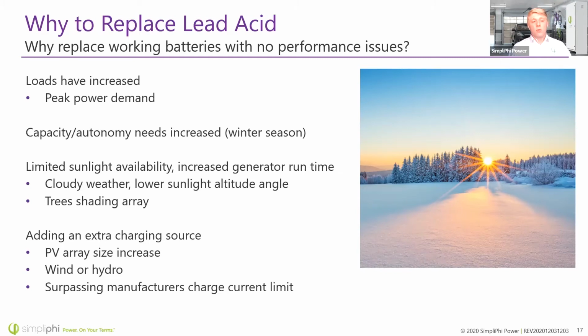You may also need to upgrade if you're adding an extra charging source. A lot of people don't consider the charge and discharge current rating of a battery—they just consider capacity. But if you're adding to your PV array size, or adding a wind turbine or hydro turbine, you could end up surpassing the manufacturer's charge current limit for the battery. In that case, you'd need to increase the size of your battery bank or change it altogether.